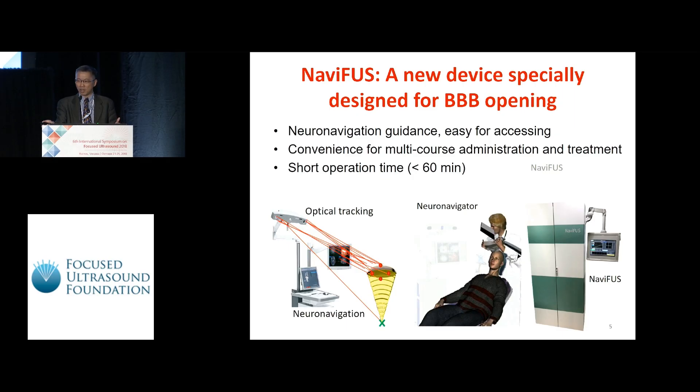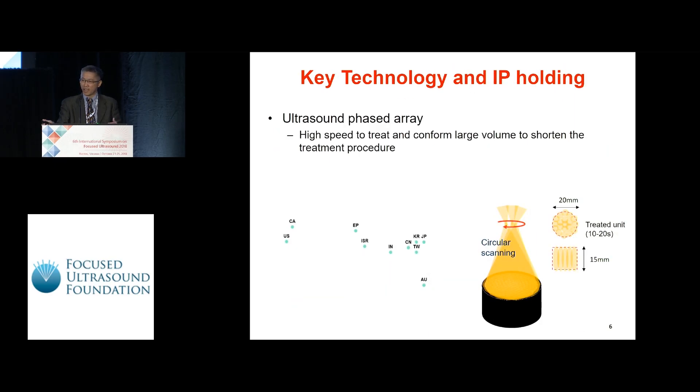First, we use an optical tracking system plus a commercial neuro-navigator to guide the focused ultrasound energy helmet, so the surgeon can easily and manually move the helmet to the pre-planned target and focus on the patient's head. It is convenient for patients to undergo multi-course administration because we don't need an MRI machine, and the operation time is very short — less than 60 minutes. The second technology uses software and hardware to shift the energy from a single cylinder to a multi-cylinder array, forming a volume of 20 by 15 millimeters, which helps to enlarge the coverage area for brain tumors.